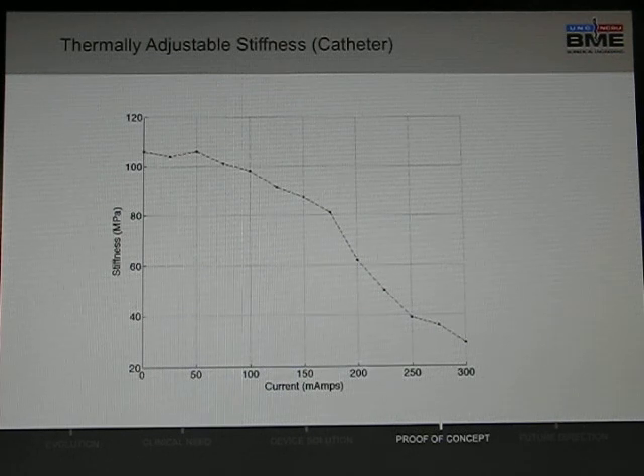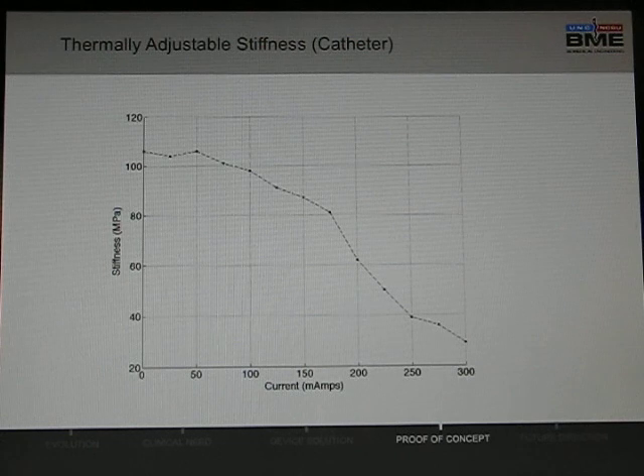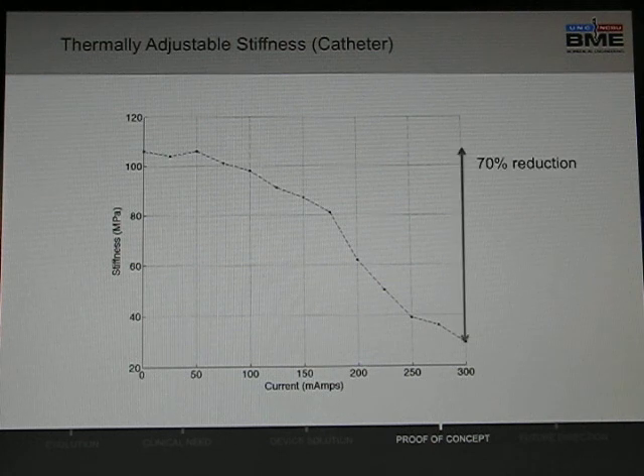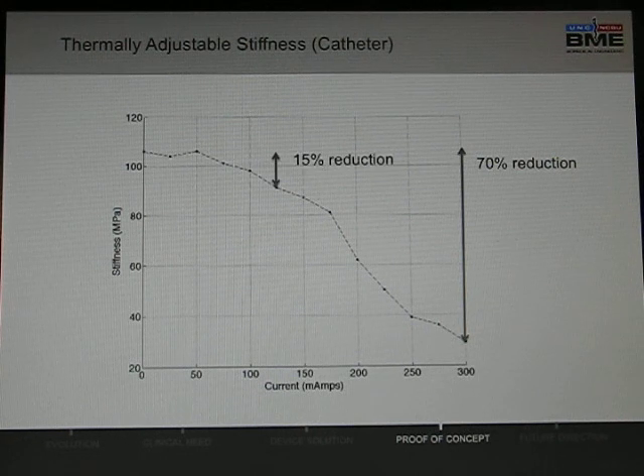Here we plotted stiffness over the range of currents applied, and you can see we get a similar sigmoidal type distribution like that for the adjustable stiffness tubes. There was approximately a 70% reduction in stiffness from inactive state to an active state of 300 milliamps. Once again, you see a 15% reduction similar to the market catheter range with 125 milliamps of current, which corresponds to a catheter surface temperature of 40 degrees Celsius.